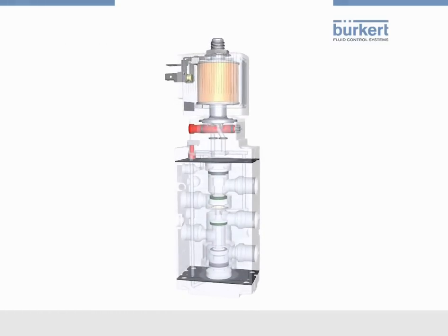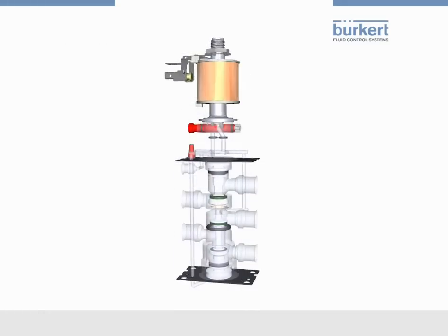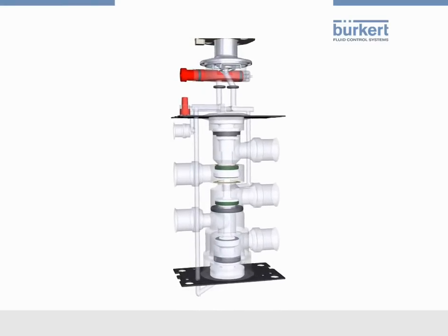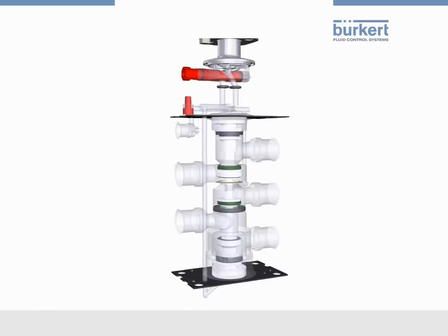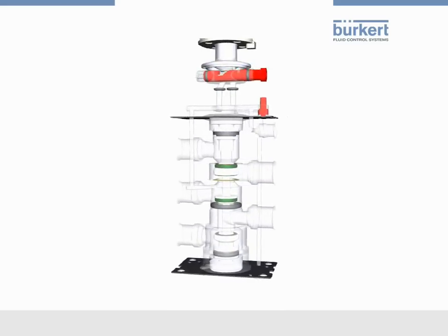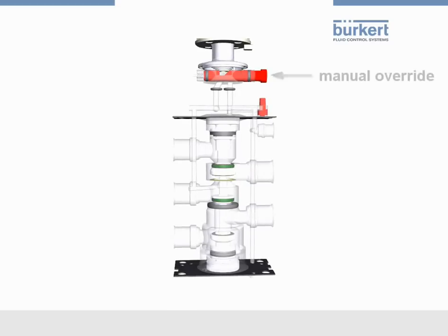In general, Type 6519 consists of a servo-assisted valve Type 6014 and the pneumatic amplifier. The housing consists of a piston, 2 diaphragms, various sealings, and 5 pneumatic connections. Moreover, we have a manual override and a position indicator. Now we see how the valve works.